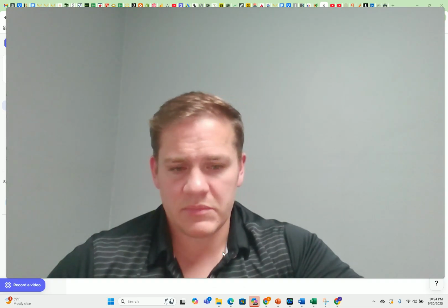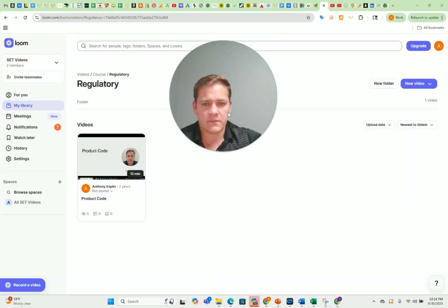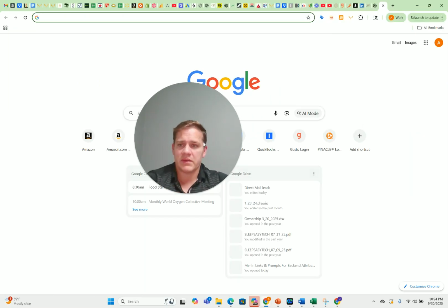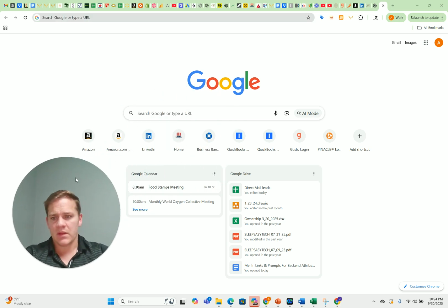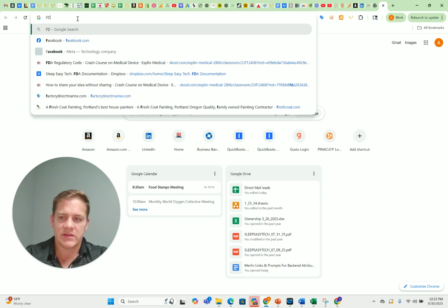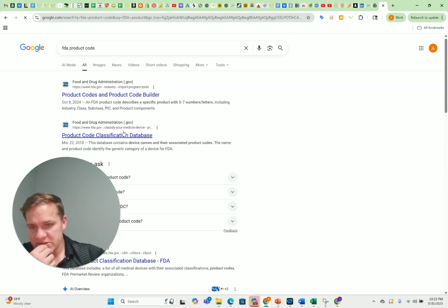So if I open up a new tab, let me shrink myself here. There we go. Don't mind all of the many tabs I have open. I've always got a million tabs. So the first place you're going to want to go is the FDA website to find the product code. It's pretty simple to get there.